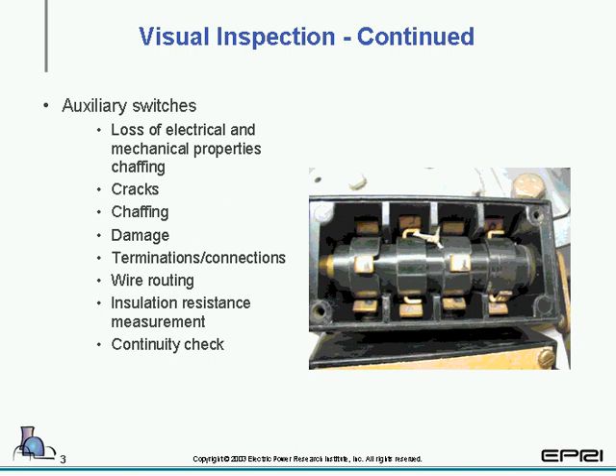Auxiliary switches. We have a list of items to look for, and care must be taken if replacing. The contact sequence may not be the same as one pulled out of stock as one that is already on the breaker. And you need to verify orientation of your A's and your B's before and after installation of your auxiliary switches.